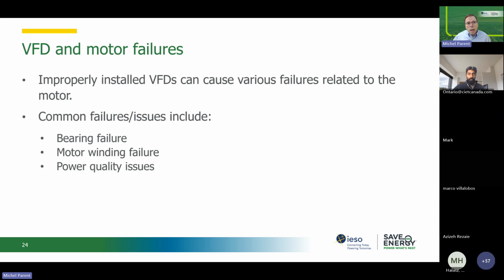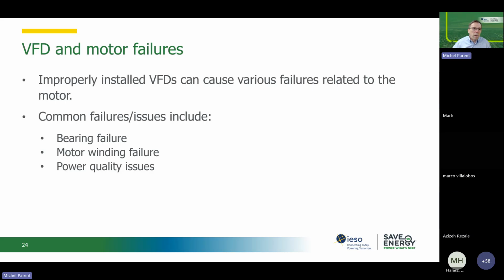The other issue with VFDs, if it's not installed properly, is premature bearing failure. It is a very common issue with VFDs, because there's current, there's voltage that will build up in the bearing, and it will eventually pit the bearing surface. It's called fluting, and it will create bearing failure. Motor winding failure, I just talked about it. If you don't have an inverter duty motor, it is likely that your motor winding will fail. And the last one is not a failure, but it's a power quality issue that most people are aware of because of the harmonics that are fed back into your electrical system from VFDs.